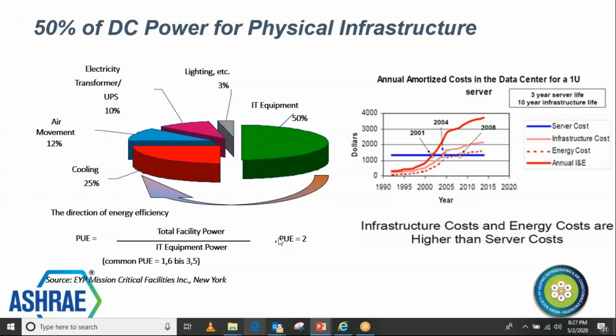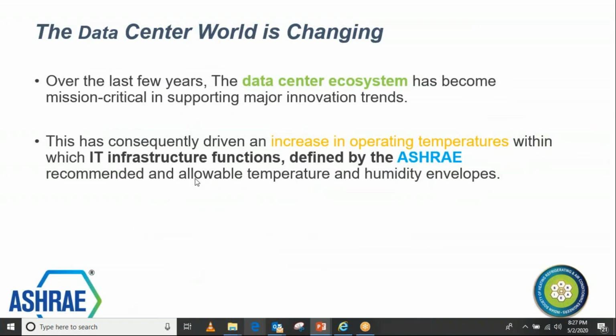1.25 to 1.5. Obviously, the PUE will also depend on the ambient, because the ambient plays a major role. Outside India, you can have a data center with 1.1 PUE because your ambient is so low. But in India, it's very difficult to achieve those kinds of PUE levels. Okay. So what is driving this, we learned in the previous slide.